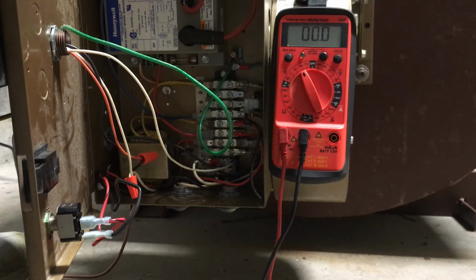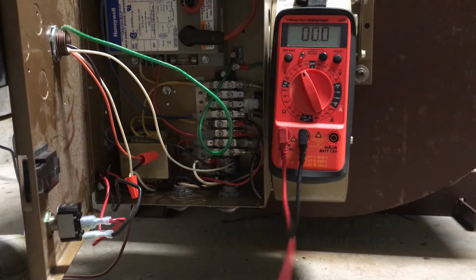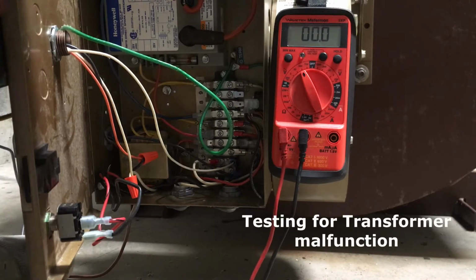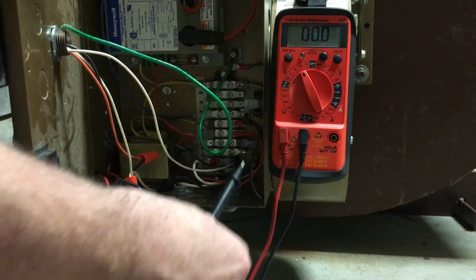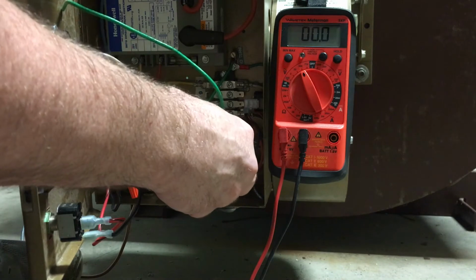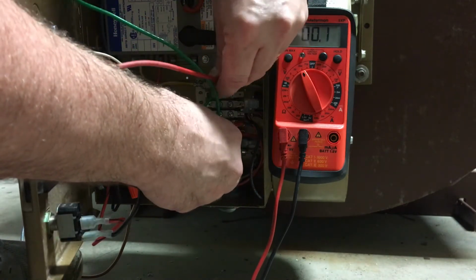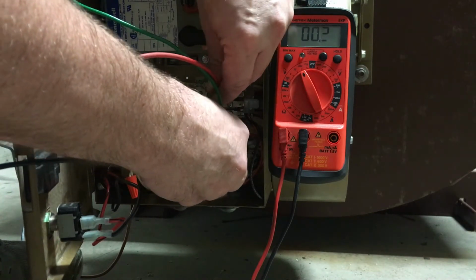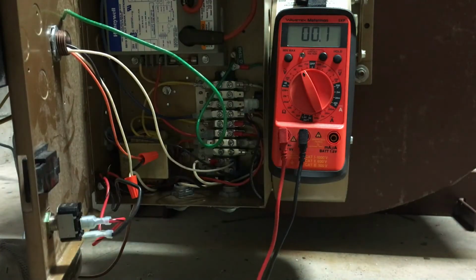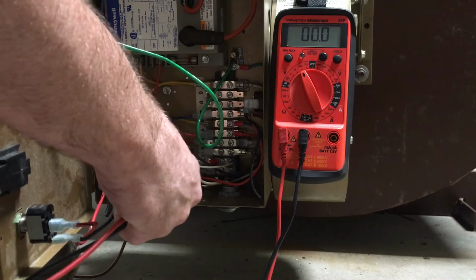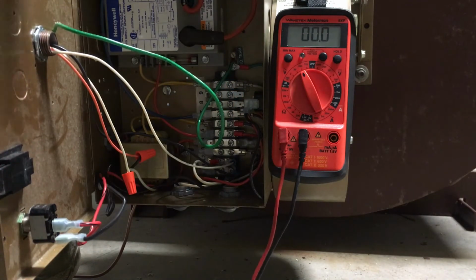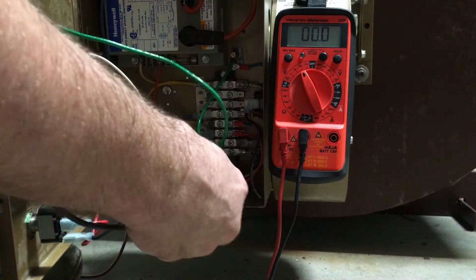So we'll check the 24 volt between terminal strip 6 and 10, and that indicates whether the transformer is operating properly. Again, you need to do this all as if the system is operating, as if it's supposed to be running. So we'll go through 6 and 10. See, I'm not getting any voltage through there. That means the transformer is not sending out the proper voltage. So you need to verify that it operates properly. If you need to, you can change that transformer out. But once you change that out, verify again that it is operating properly. So now the blower is running.